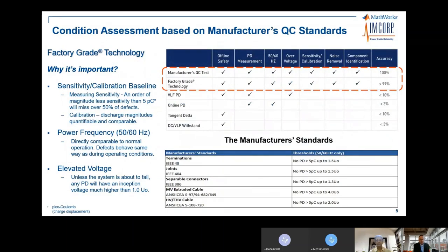Manufacturers use an offline test in their factory. They excite the cable with an overvoltage at 50 or 60 Hz sinusoidal voltage, performing sensitivity and calibration measurements to ensure the measurement makes sense. This is done in a shielded environment — a Faraday cage — so that ambient noise gets removed.